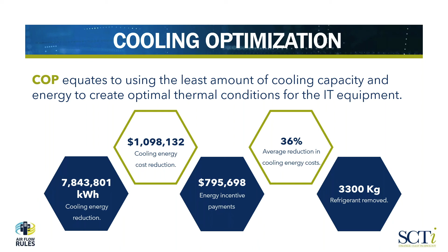To put a slightly different perspective on it, our cooling optimization program has worked in a variety of data centers: colos, large data centers, small data centers. On the colo side, typically our average is running about a 40% energy reduction, and we've averaged about 274 kilowatts of additional IT load, enabling this IT load to be added to a site without the addition of more cooling.